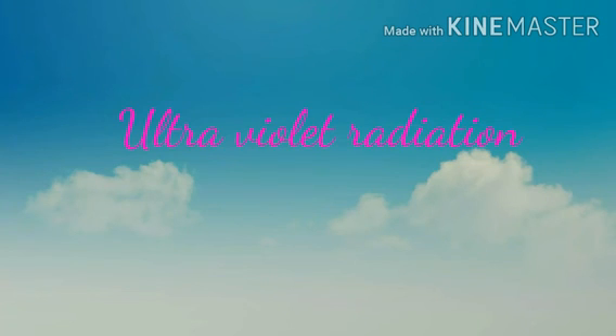known as ultraviolet radiation. The invisible ultraviolet rays are very effective in killing all types of bacteria. This method is widely used for disinfection of swimming pool water because it does not require any chemical to mix with the water. In this method, ultraviolet rays from mercury lamps or quartz globes are simply focused on the flowing water. However, this method is very costly and cannot be used for municipal water supply.